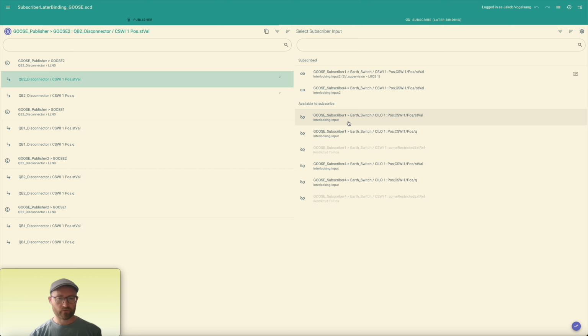So you can already upfront say, I am expecting specific data to come in, and this data I already linked to internal functionality. In SCL expressed as the external reference has no reference to the data it's subscribing, but it has an internal attribute, an internal address attribute, sorry, that is pointing to the internal function of the IED.